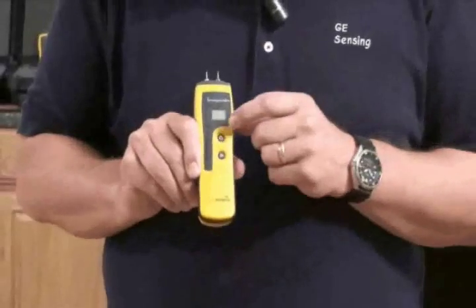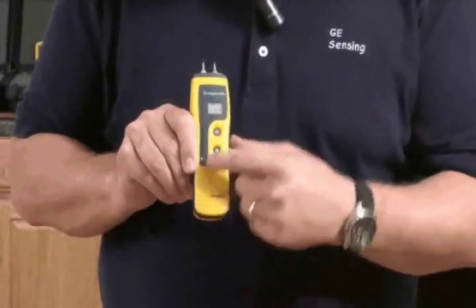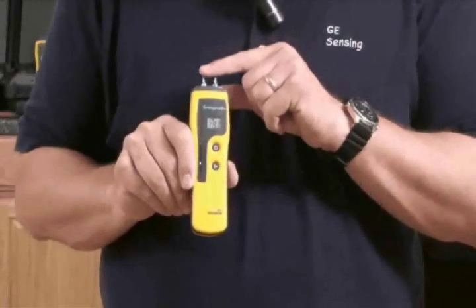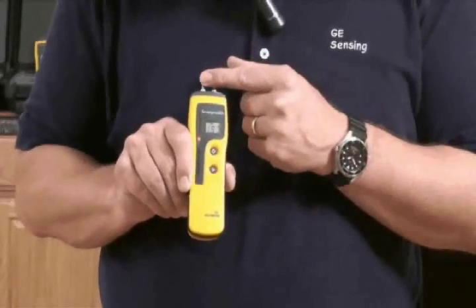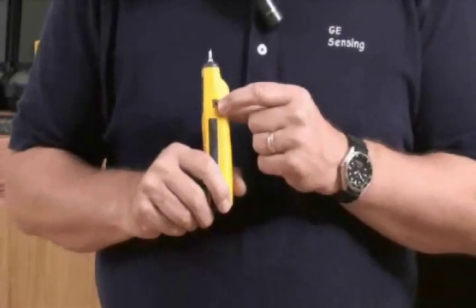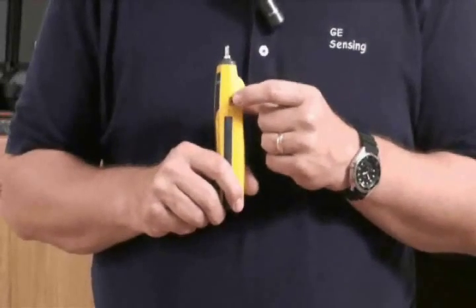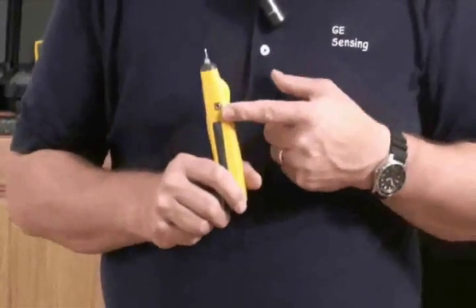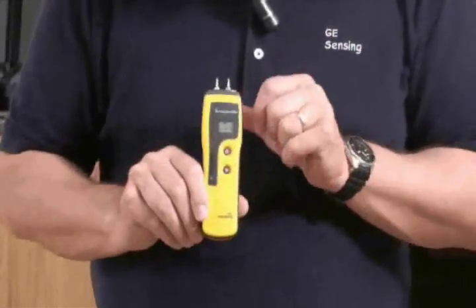The first thing we'll look at is the pin mode. When I turn it on, you'll see there's a green light, and when we make contact across the pins — replicating what you would do when you push the pins into material — you'll see the green, yellow, and red lights, as well as a numeric value. In pin mode, you can also use accessories via the jack plug, including the deep wall probes, a probe for hard-to-reach areas, and a range of other Protimeter accessories like hammer electrodes for hardwood floors and softwoods.